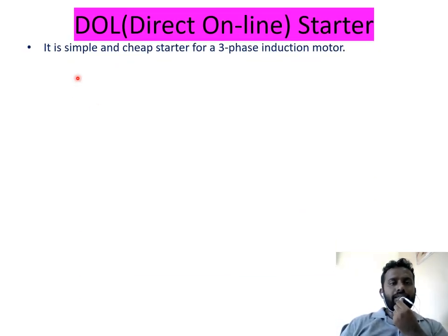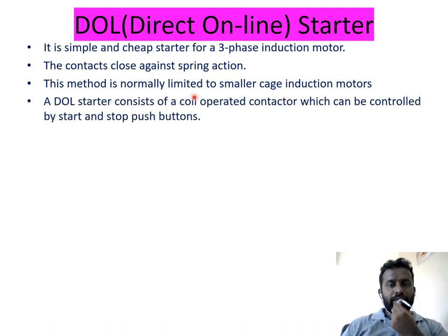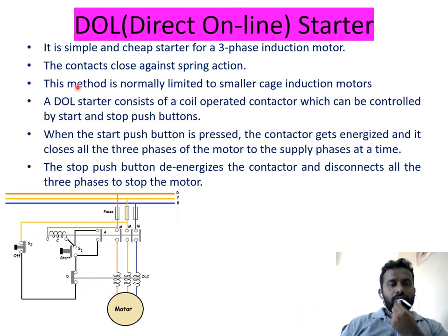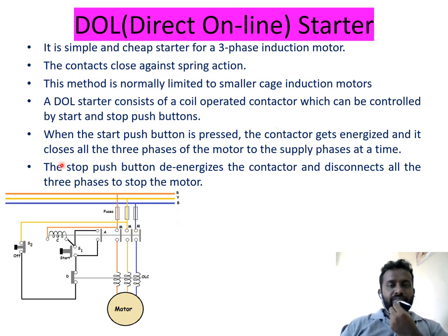DOL — Direct Online Starter: it is a simple and cheap starter for three-phase induction motors. This method is normally limited to small cage induction motors. A DOL starter consists of a coil-operated contactor controlled by start and stop push buttons. When the start push button is pressed, the contactor gets energized and closes all three phases of the motor to the supply. The stop push button de-energizes the contactor and disconnects all three phases to stop the motor.